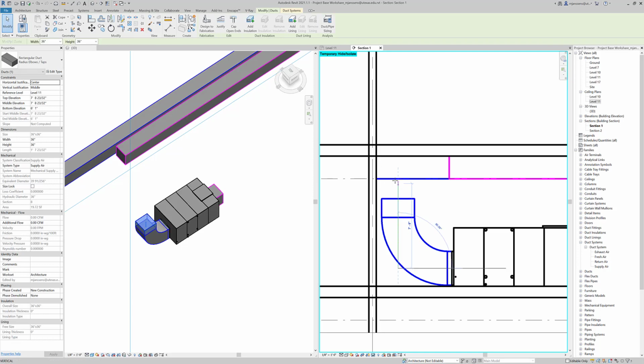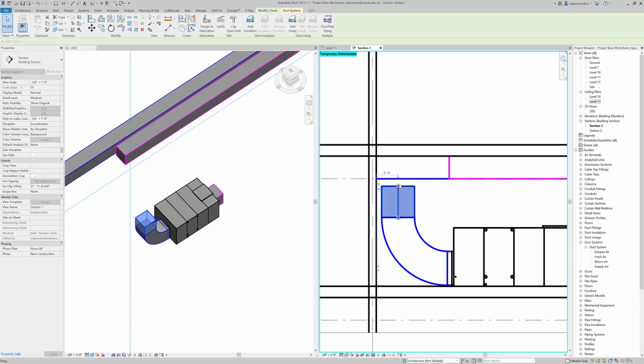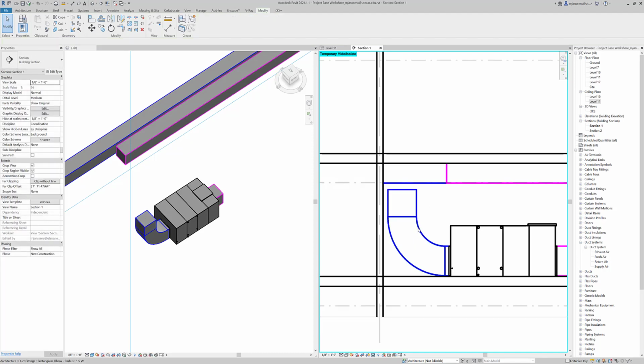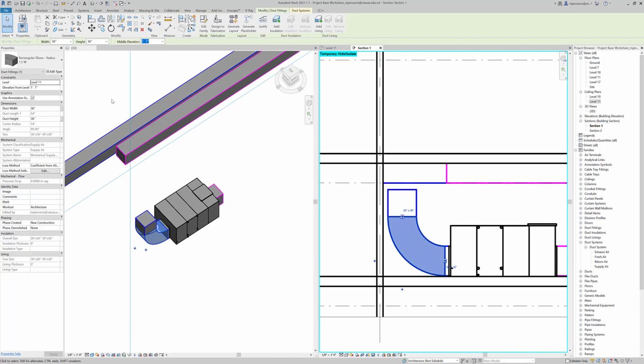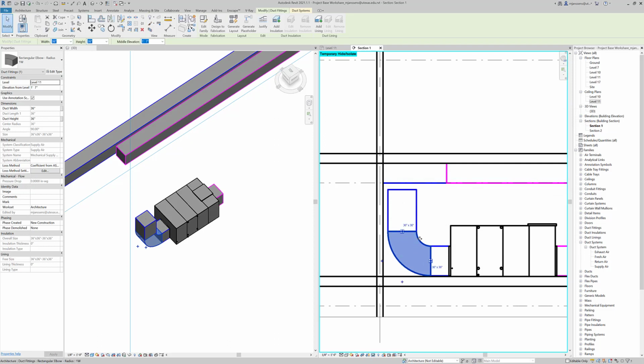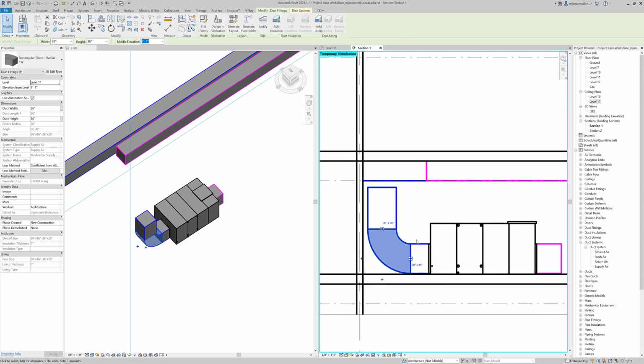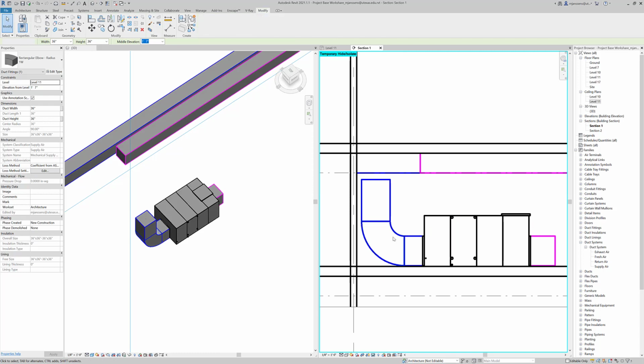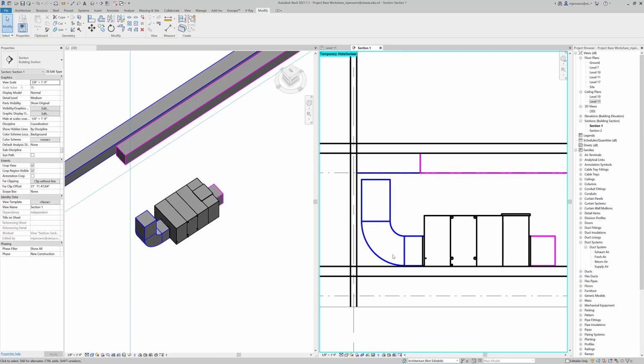It might be a case that there's not enough room this way either, so you might have to increase the size of that duct. Now this elbow is quite big. It's 1.5 times the width of the duct. So we can actually change this to 1. We can edit this type, and we can actually change the rules. So you probably want to edit the type of the radius, duplicate it to a 1W, and change that to a 1. So that you can get a much tighter radius here. The tighter the radius, the less efficient the duct, but it allows us to fit in much tighter spaces.